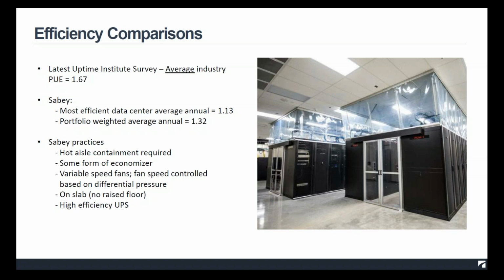And so that removes a lot of the complexities associated with the raised floor, the management of the tiles, the delamination, what's going on underneath the raised floor. There's advantages to raised floor, but if you can simplify it and move it out of the equation, you can also increase some of the efficiency, because there do tend to be some losses involved in pressurizing that raised floor and trying to get the air to the right place. And of course, I mentioned the high efficiency UPS modules. All of the recent UPS modules we have are 96% plus efficiency, and that's in double conversion mode. Next slide, please.